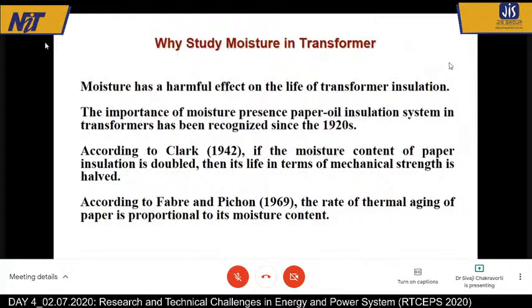One of the most important aspects found in the 1920s was that moisture is the most detrimental factor for insulation, particularly paper insulation. By the way, if oil gets deteriorated, we can change the oil. But if paper gets deteriorated, we have to change the entire winding, which means 50% of the transformer cost. So people are less bothered about oil, and more bothered about paper.